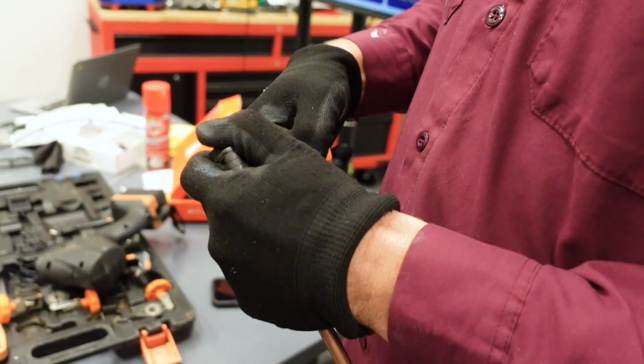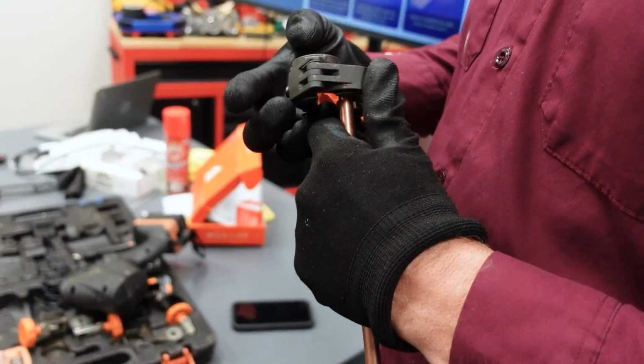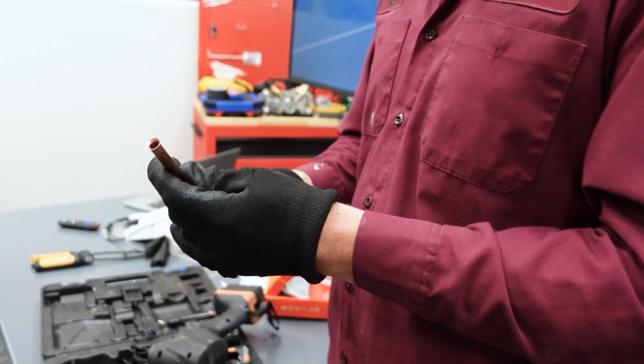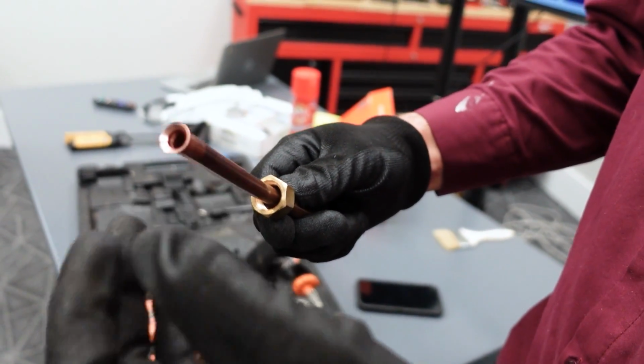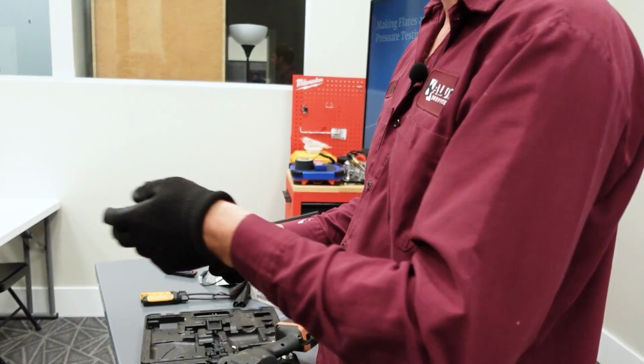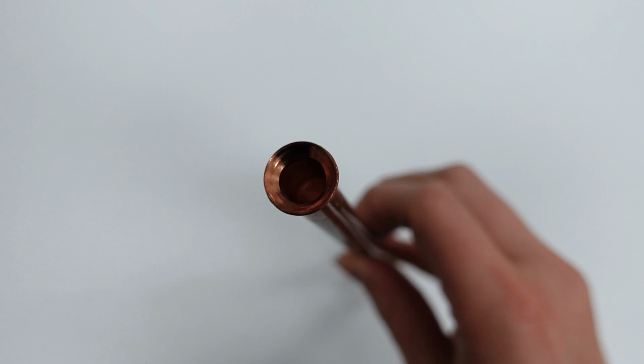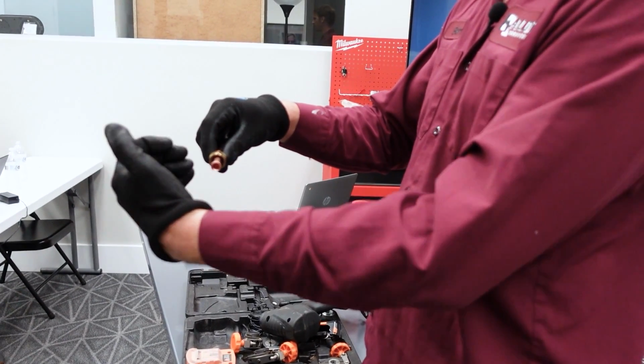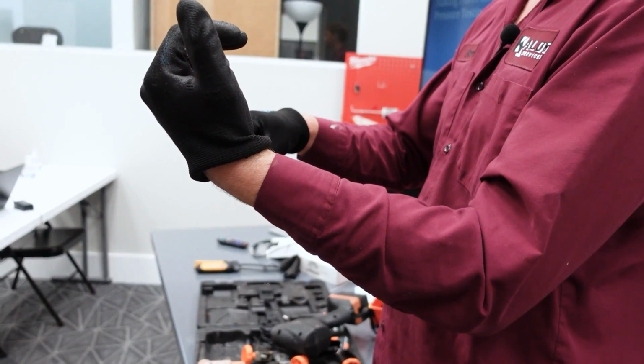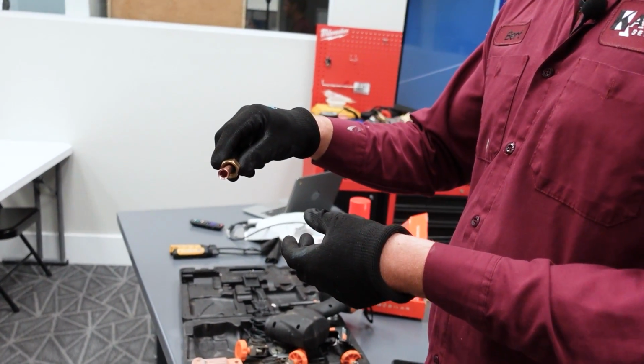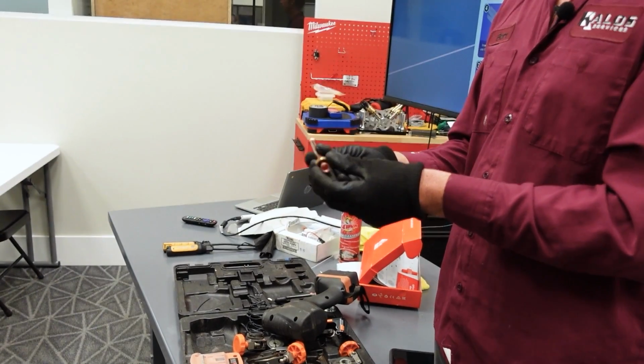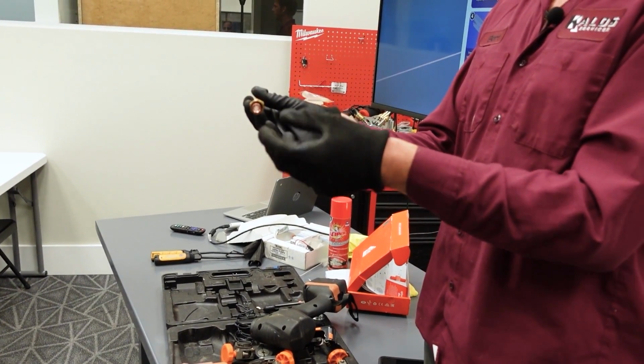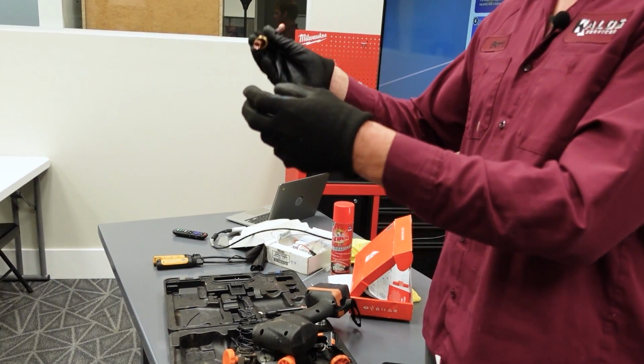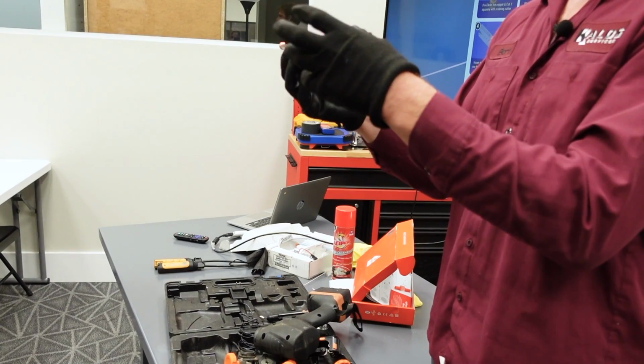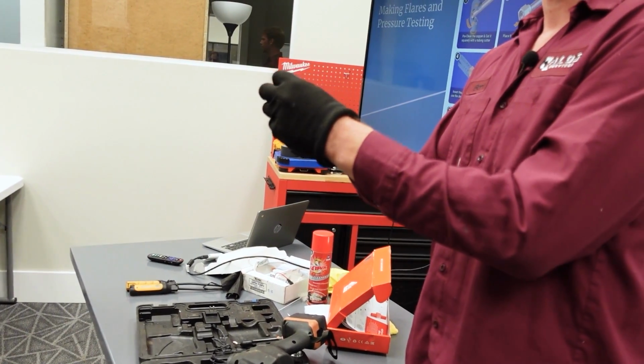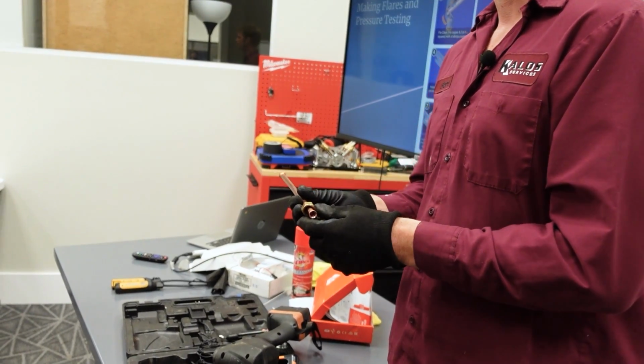Before you hook up your flare, inspect your joint and make sure it's beautiful. Give it a visual inspection, go around that top edge, make sure there's no lip folded over, pushed in, or cracked, and that it's smooth. Slide it up against the nipple you're going to, and make sure the width covers the face of that, not sticking too far into the threads, and not too short. Before you tighten down, line it up perfectly so the copper is resting right on the nipple where it should be, instead of pulling away. Because as the years go by, the system running and vibrating creates backward pressure pulling against it, which can crack the flare or pull it out and create a leak.